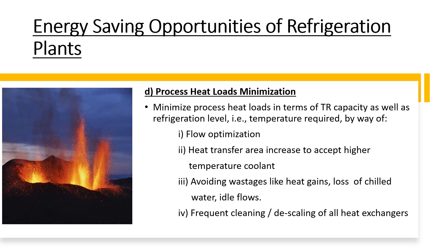The next one is process heat load minimization. Minimize process heat loads in terms of TR capacity as well as refrigeration level. This includes flow optimization, heat transfer area increase to accept higher temperatures, avoiding heat gains, loss of chilled water, idle flows, and frequent cleaning and de-scaling of all heat exchangers.